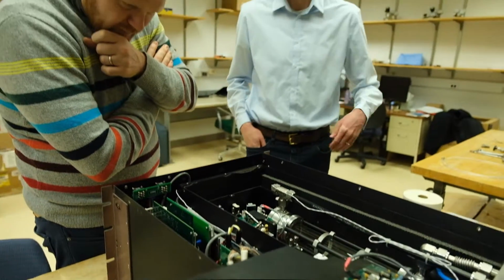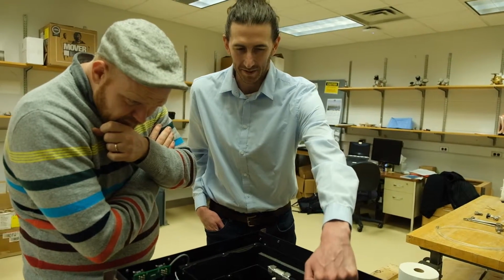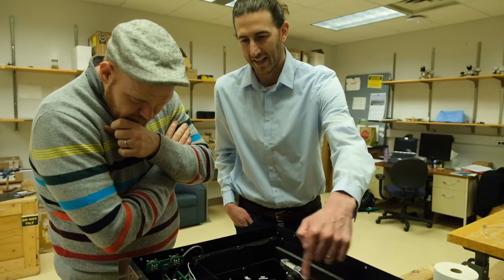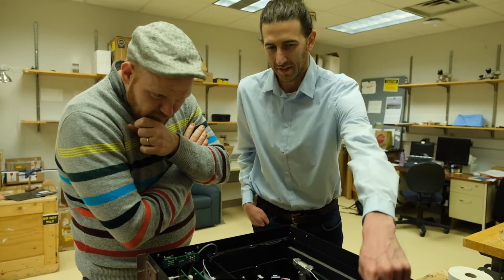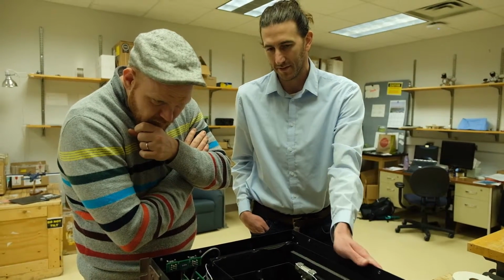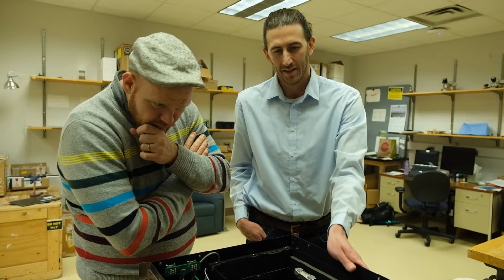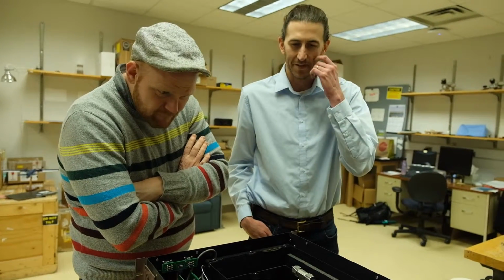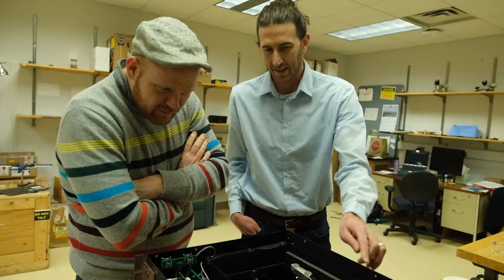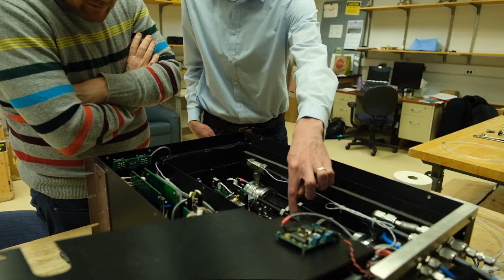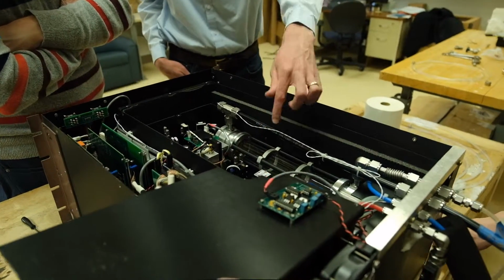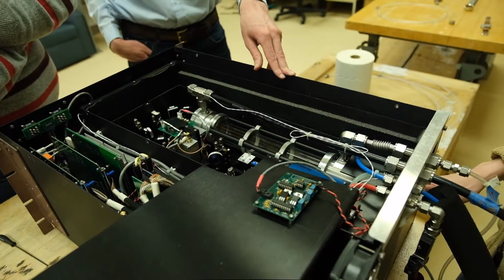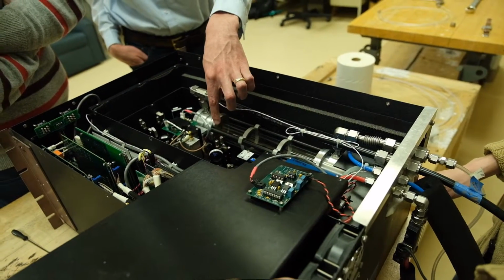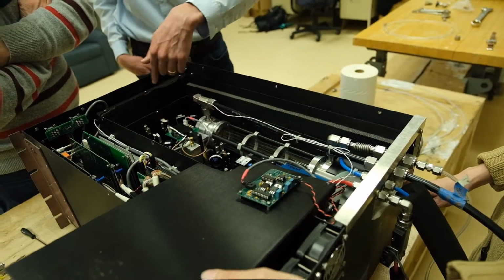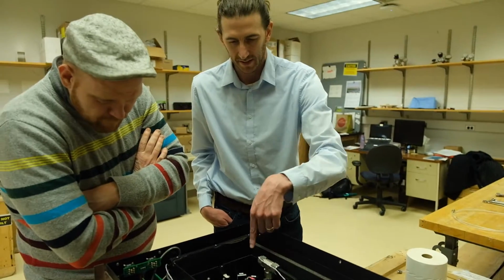So yeah, you see, this is a visible trace laser, which is just used for helping to actually set up the alignment, because this laser is invisible. It's in the infrared, so it's harder to set up all the mirrors for something in the infrared. So yeah, it gets collected on this. It's like a microscope objective mount. It's like a reflective objective that focuses it. It basically makes its way down here, goes to the cell, and then comes back out and onto the detector.